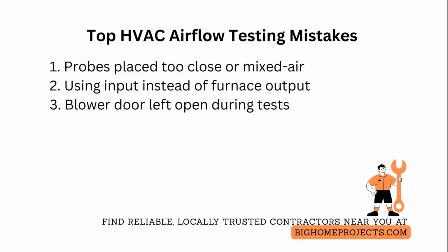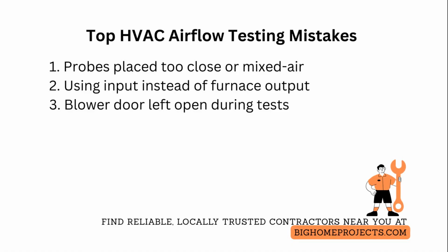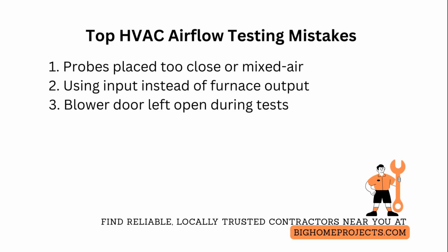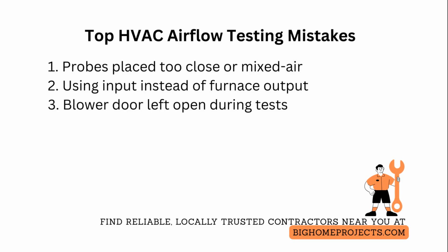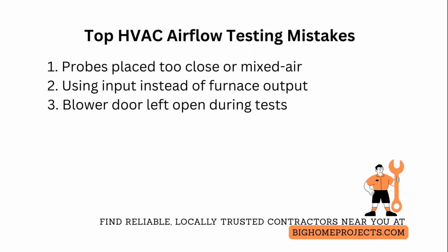One of the frequent issues with airflow measurement during heating is leaving the blower door cracked open, which throws off static pressure and duct airflow balance and makes the temperature rise wrong. Fix it by keeping the blower compartment closed and sealed during temperature and pressure readings, and only open the electrical compartment for quick voltage and amperage checks, so airflow remains undisturbed while you still have safe access to measurement points.